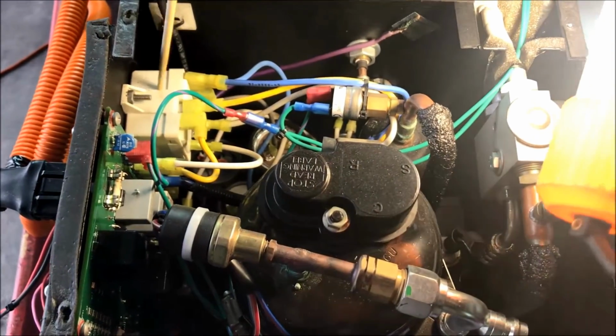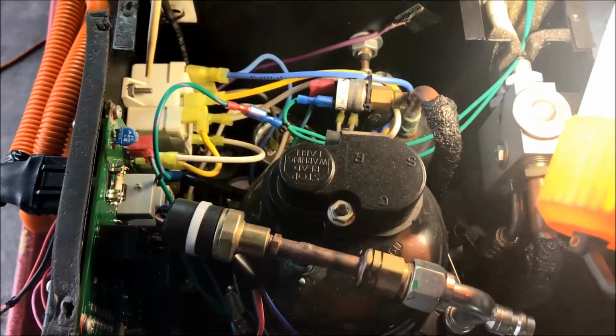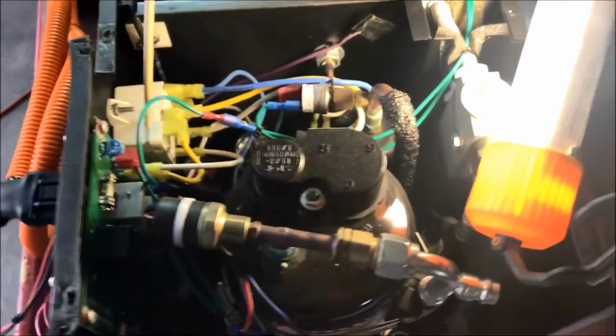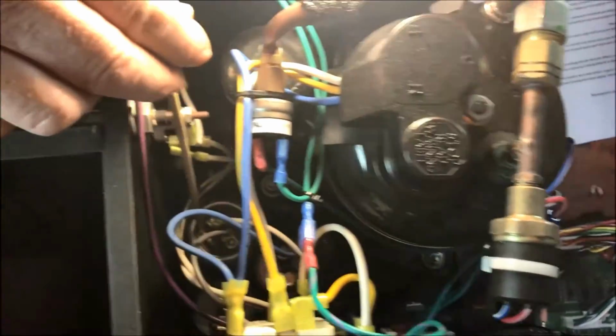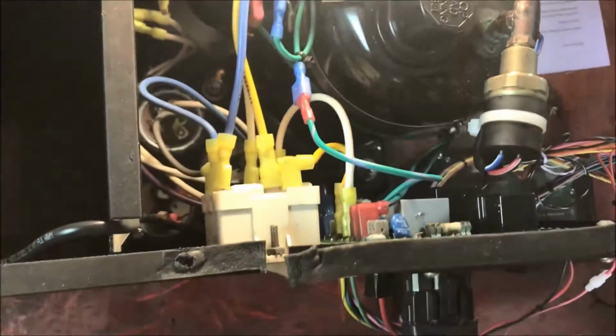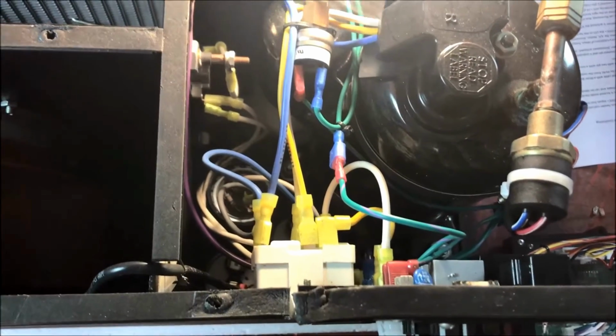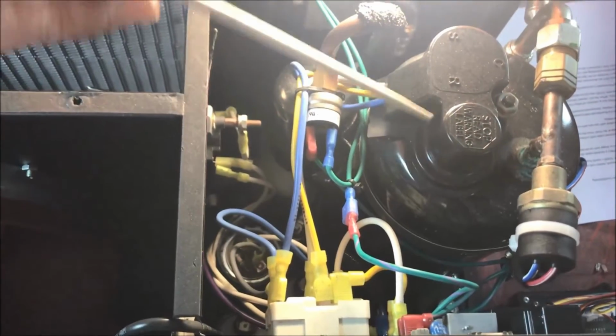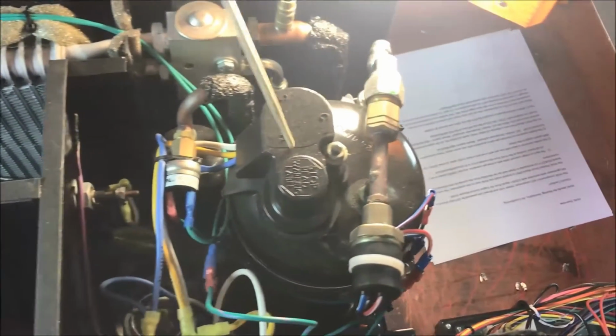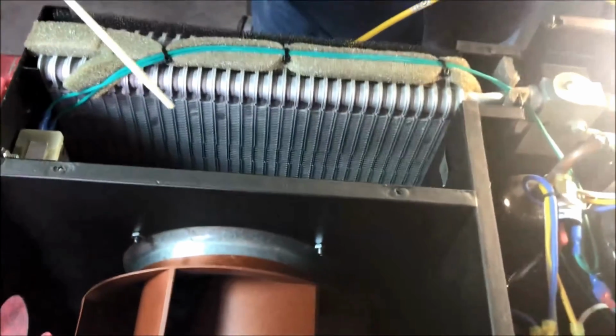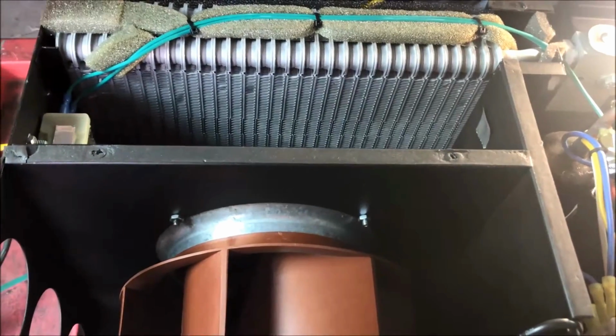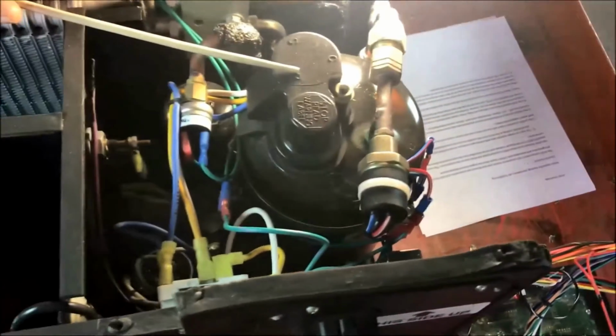This component is called the potential relay. It switches from the start capacitor, which is this large black one down here, to get the compressor moving. Then it switches to the run capacitor, which will keep the compressor moving at a lower power supply. And the AC system is just like an automotive mechanical compressor, except the compressor is electric.